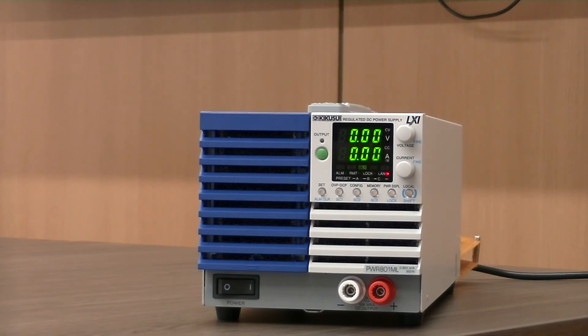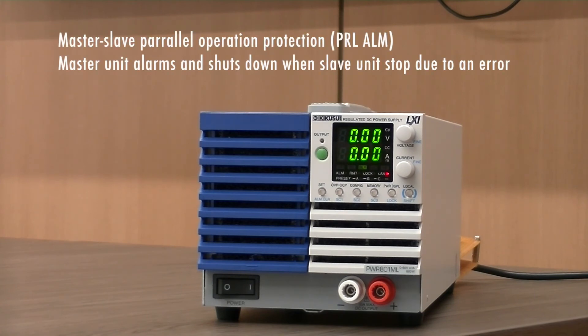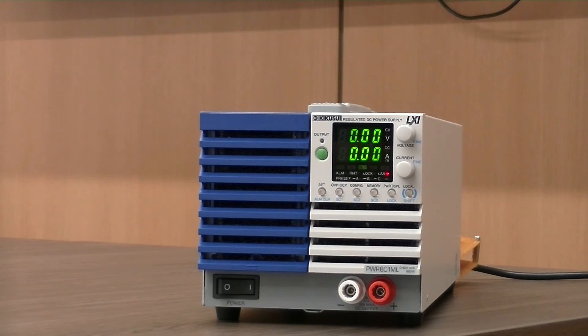Last, but definitely not least, is the master-slave parallel operation protection. If a slave unit stops due to an error during master-slave parallel operation, the master unit detects the alarm and shuts down the output of the entire system. This function protects devices by preventing the master unit and the remaining slave units from continuing output.